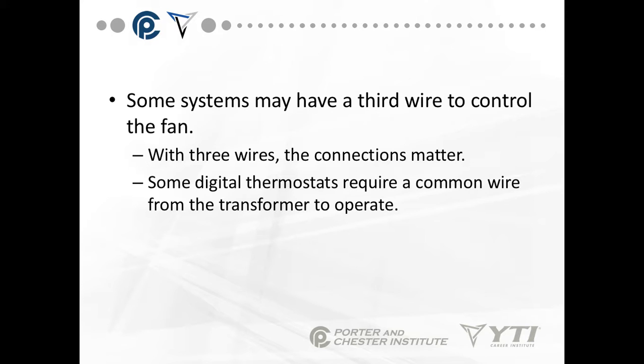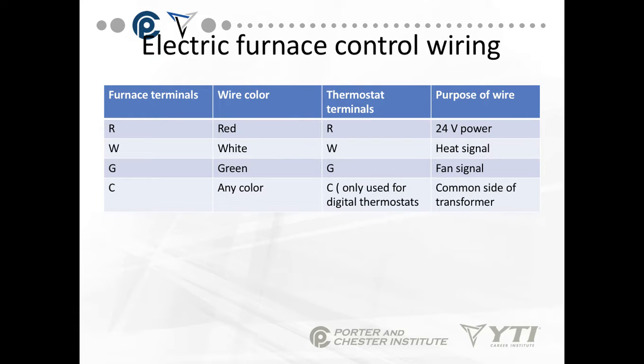Some systems may have a third wire to control the fan. With three wires, the connections do matter. Some digital thermostats require a common wire from the transformer to operate. So here are the furnace terminals, the thermostat terminals, and the suggested wire colors. More and more, you're going to find that it just matters that the same wire colors used on the furnace terminals are used on the thermostat terminals. R is your 24-volt power. W is your heating signal. G is your fan signal. And C is used only for digital thermostats, and it comes back to the common side of the transformer.